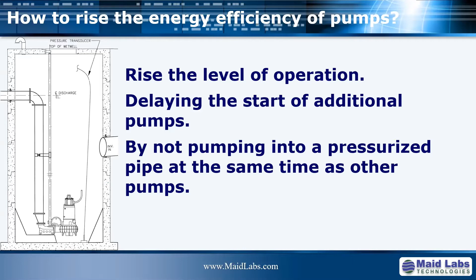Okay, this is how you can increase the efficiency of your pumps. I will explain how you can do that in a second. First, look at how a standard lift station works. You have the off level, which is usually as low as possible. You have the lead level, which should be above it so that your pump runs, let's say, something like 2 minutes, 5 minutes, something like this.